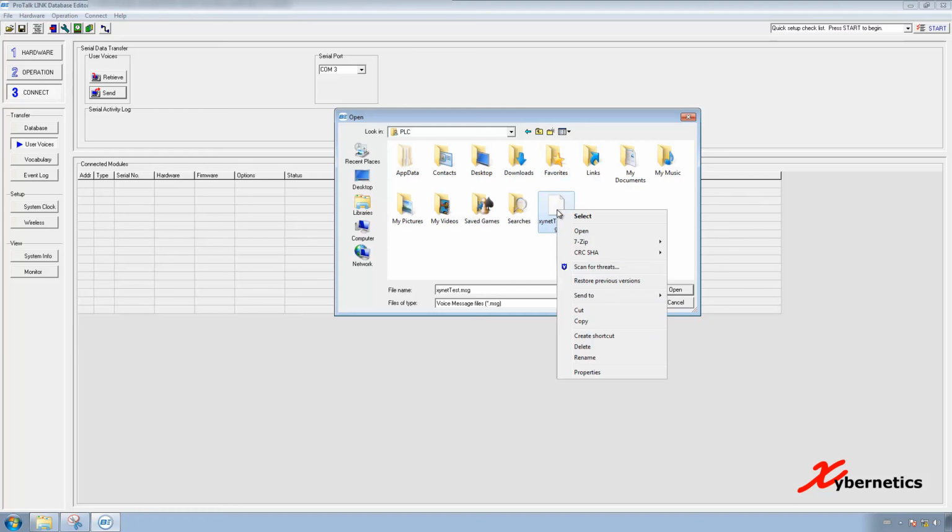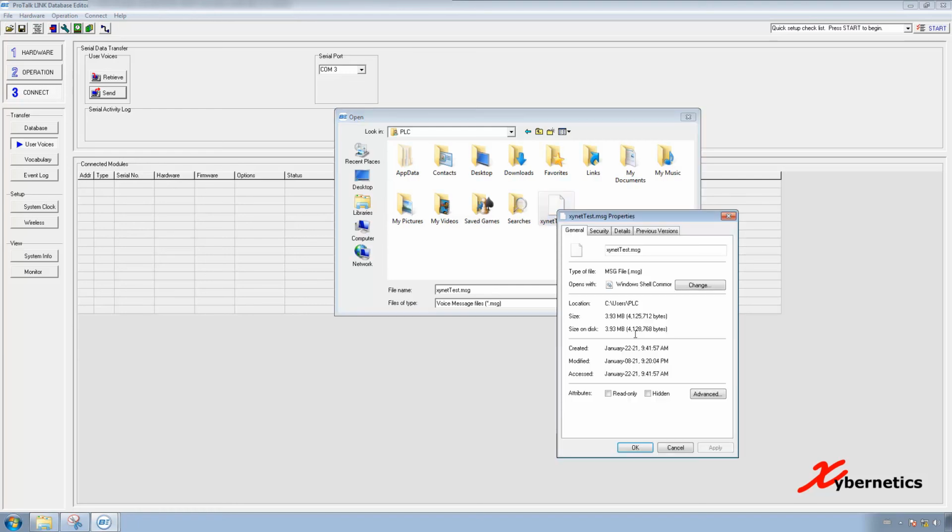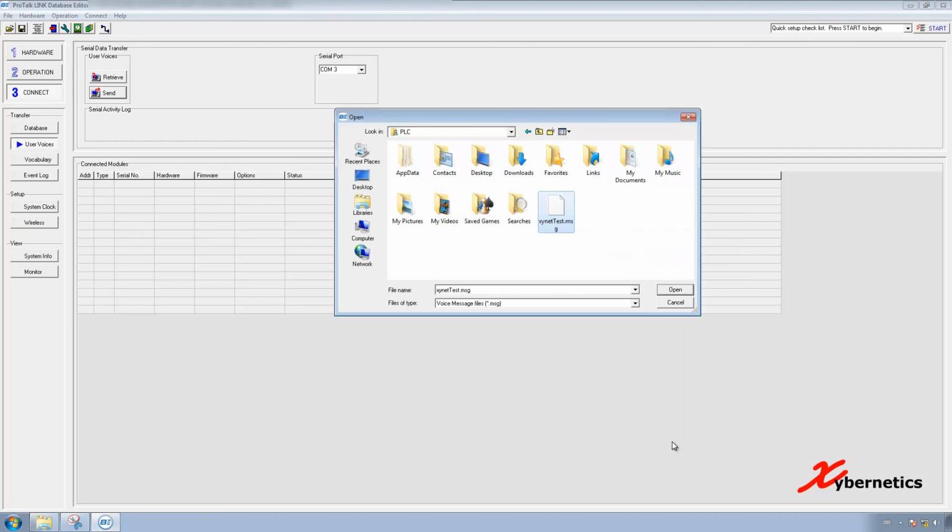Depending on how big your file is, this file is about 3 to 4 megabytes. It takes me a good 20 to 30 minutes to upload. Another thing you have to be cognizant of is that during those 20 to 30 minutes of uploading, you will not have any callout during that time. So just be aware of that. All this has to be coordinated well and communicated well with operations if you're planning to do that.